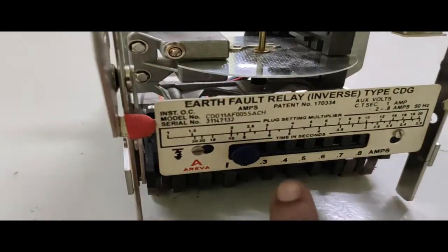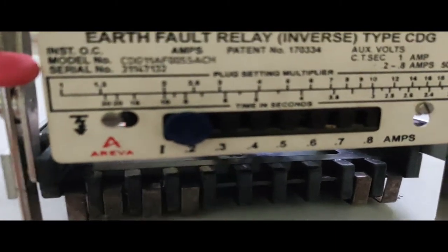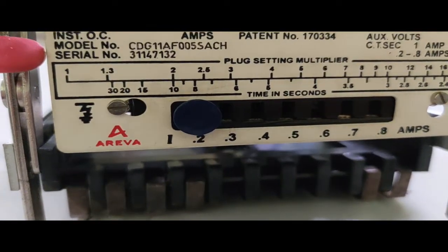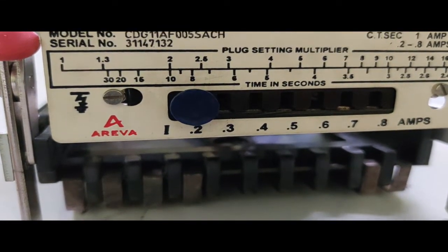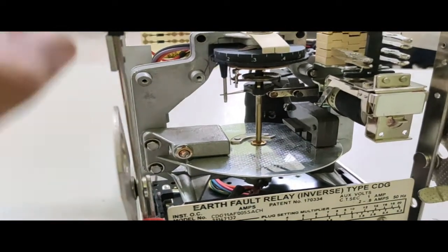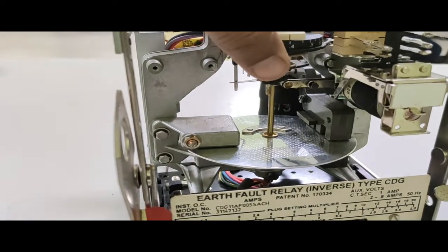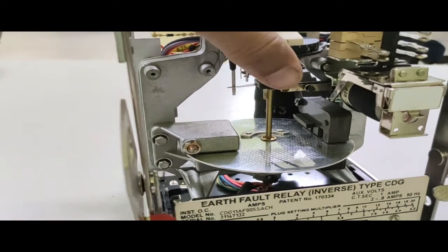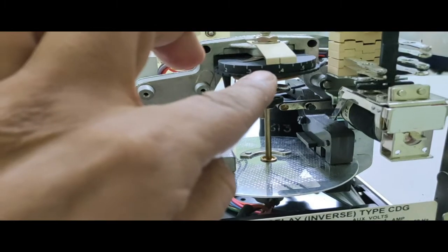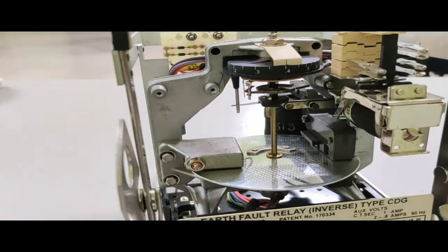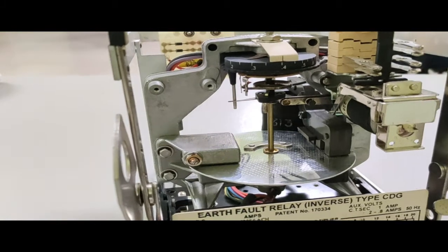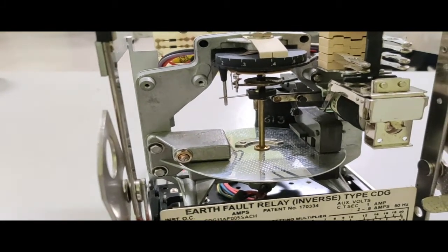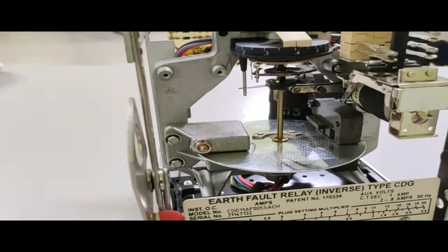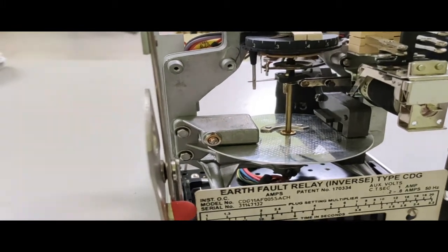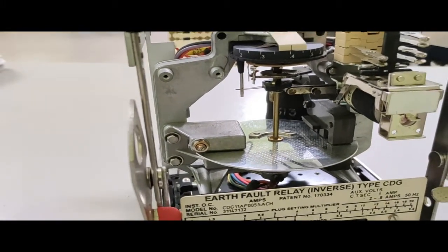It means that, say, the current setting is now at 0.2. So if the current is more than 0.2, it is expected that the relay should operate and generate the trip signal, but it should not generate the trip signal instantaneously. As it is connected to 0.4, the time setting multiplier is 0.4 right now. So after some time the relay will generate the trip signal. So in this way some intentional delay is there. When the current is more than the preset value, after that intentional time given to the relay, it will generate the trip signal.